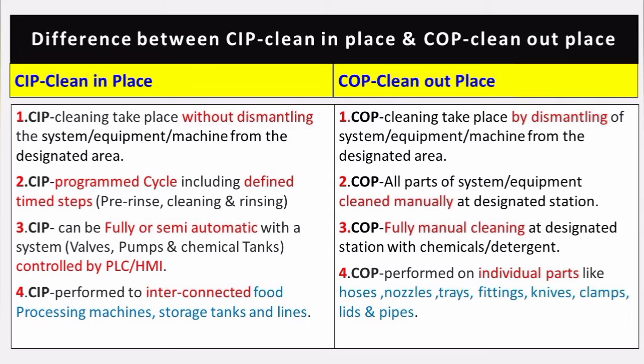CIP can be fully or semi-automatic with a system including valves, pumps, and chemical tanks, controlled by a PLC or HMI. COP, on the other hand, is fully manual cleaning at a designated station using chemicals or detergents.